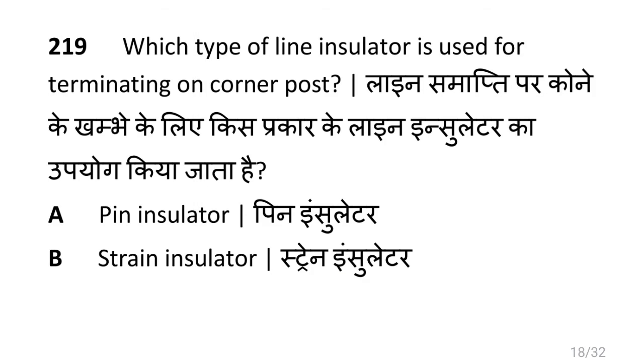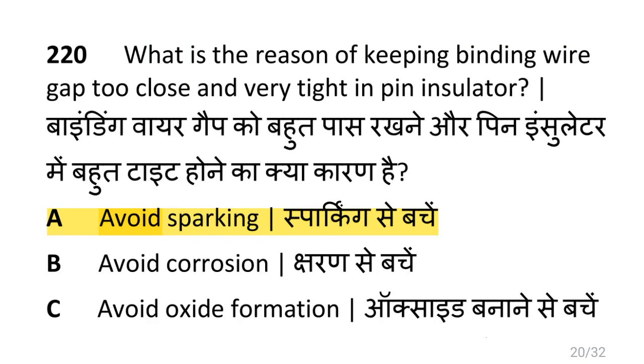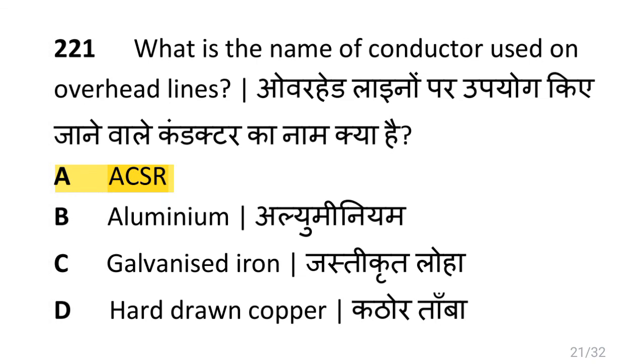Which type of line insulator is used for terminating on corner post? That is shackle insulator. What is the reason for keeping binding wire gap too close and very tight in pin insulator? That is to avoid sparking. What is the name of conductor used on overhead lines? That is ACSR.